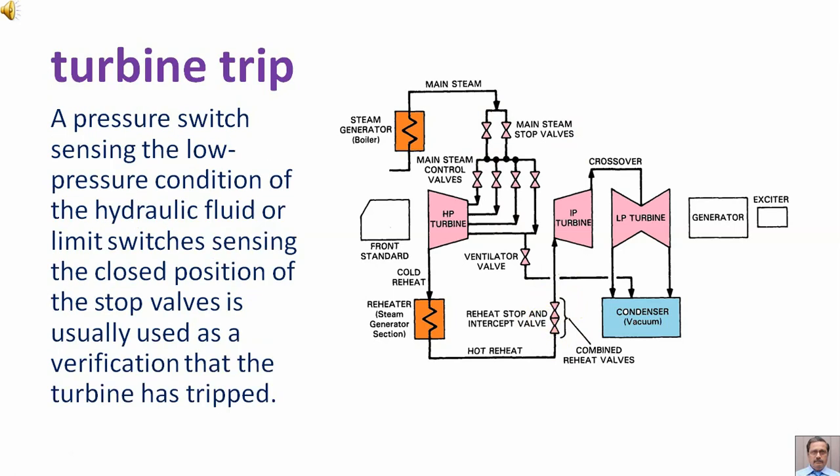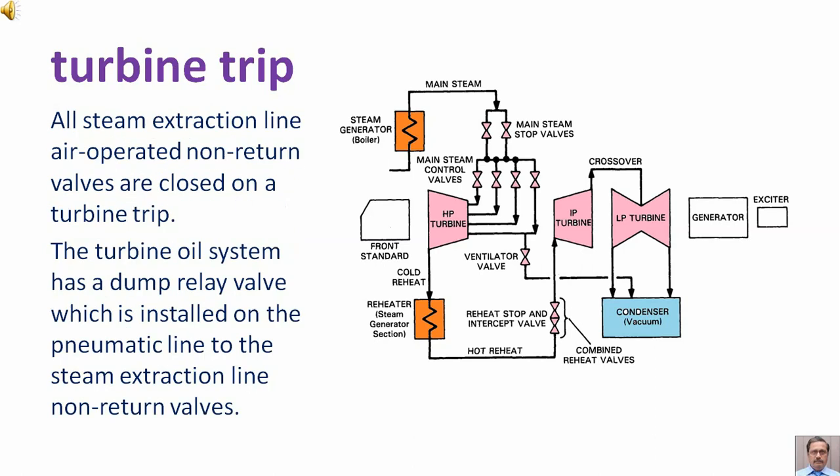A pressure switch sensing the low pressure condition of the hydraulic fluid, or limit switches sensing the closed position of the stop valves, is usually used as verification that the turbine has tripped. All steam extraction line air-operated non-return valves are closed on a turbine trip. The turbine oil system has a dump relay valve installed on the pneumatic line to the steam extraction line non-return valves.